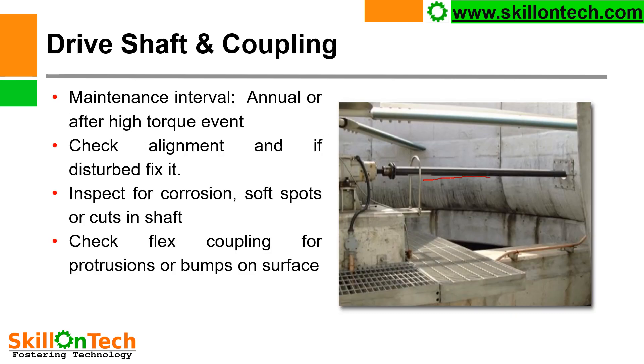Here you can see the drive shaft, coupling, and gearbox. Maintenance interval is generally annually or after a high torque event. Check alignment, and if disturbed, fix it. If any misalignment is found, the vibration level of the motor will increase, so we should check the alignment of the motor with the gearbox and maintain it. Inspect for corrosion, soft spots, or cuts in the shaft. If the drive shaft or coupling is found damaged, they shall be replaced.